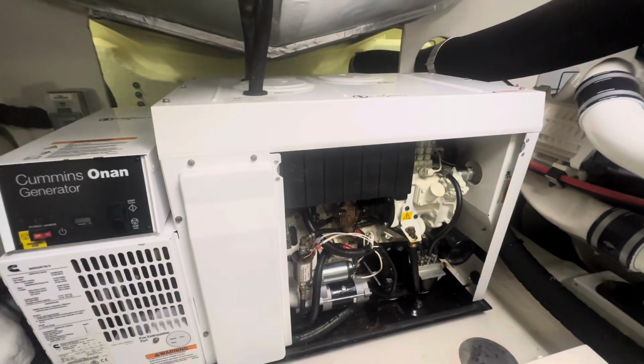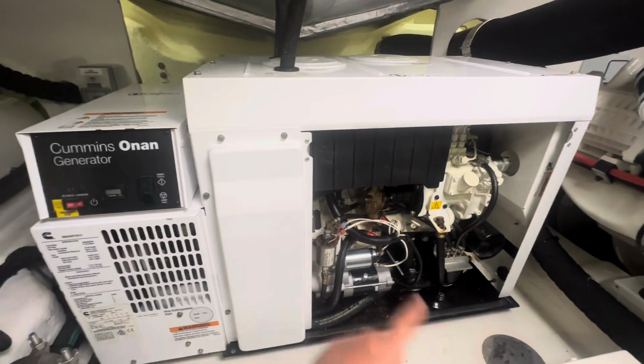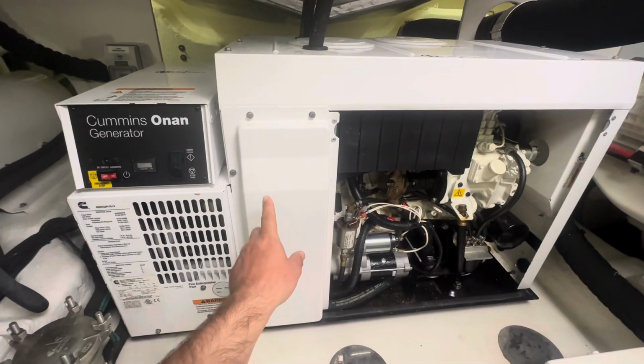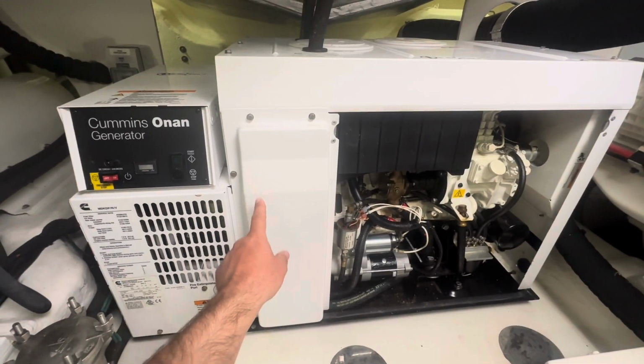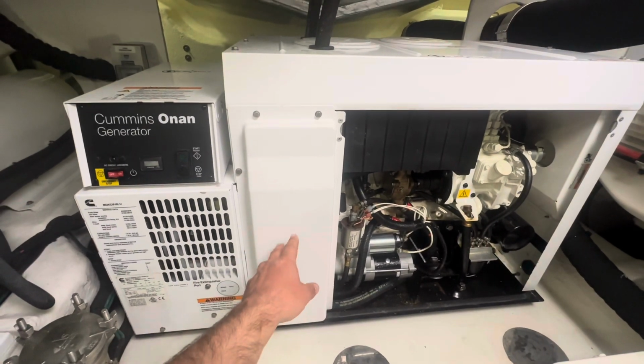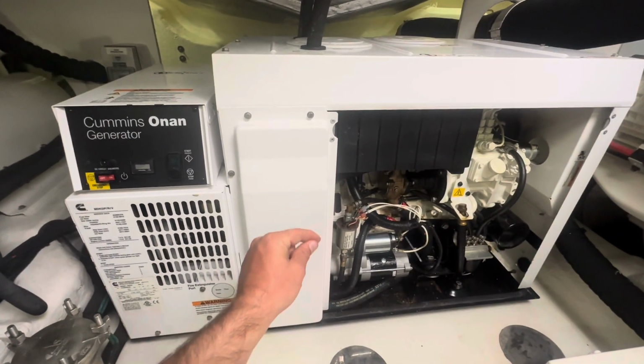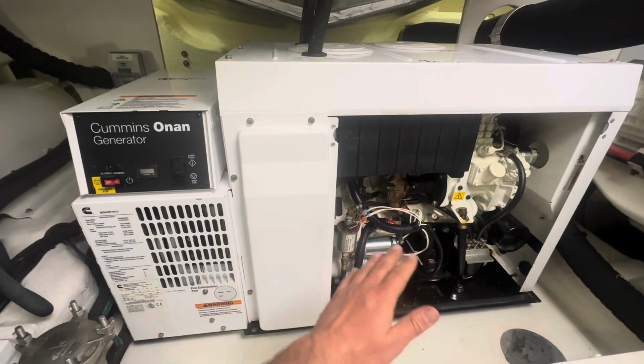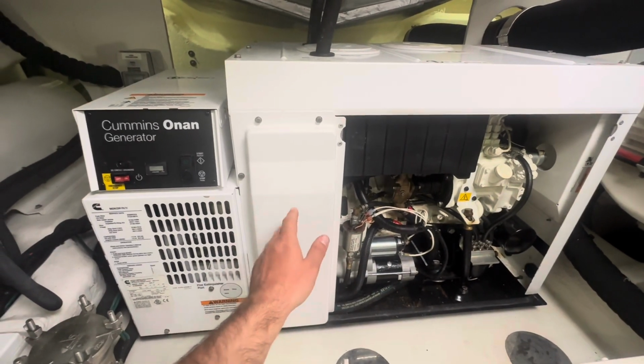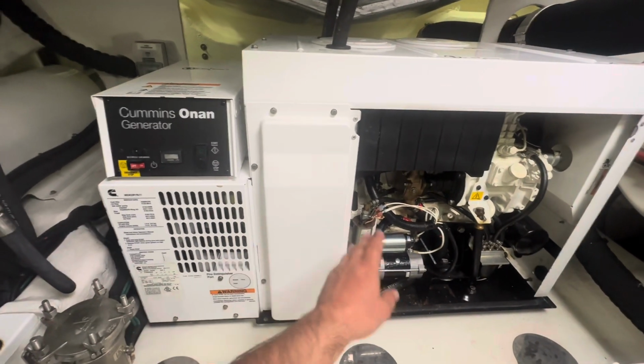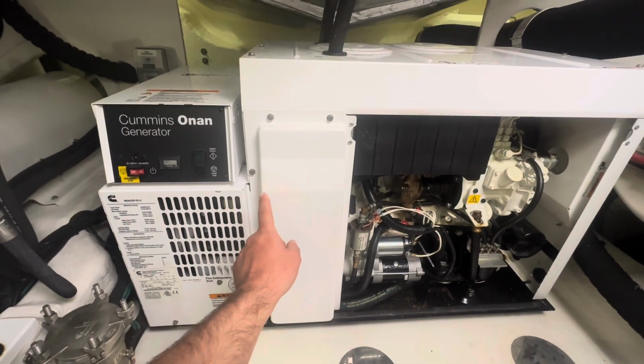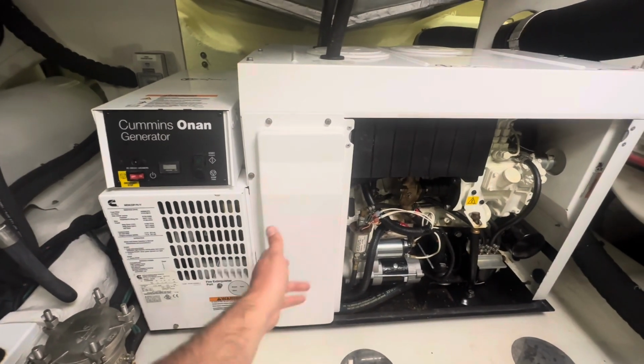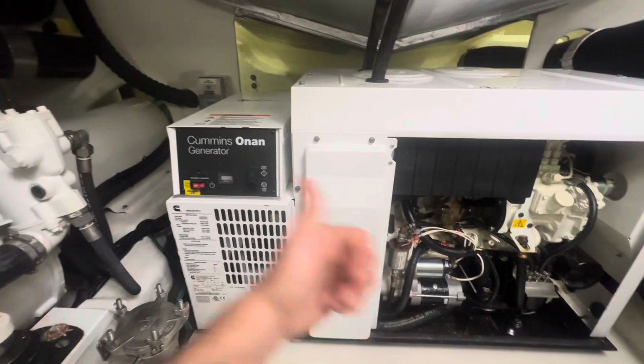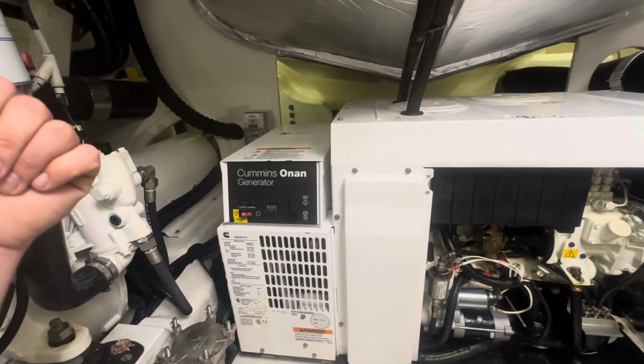Then I looked up the spec in the service manual for what this generator considers high voltage, and it's 32 volts. So if the generator reads over 32 volts at its sensor, the ECU shuts it down and throws that code. Right off the bat, without the charger on, my volts at the batteries were good at the auxiliary bank.